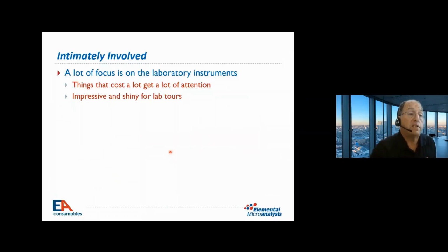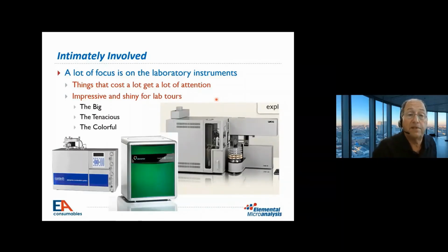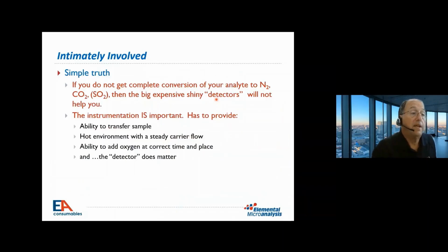But a lot of focus is always on the laboratory instruments. That's because these things that cost a lot get a lot of attention, and they're impressive and shiny for laboratory tours. There's big ones, there are tenacious ones, and there's colorful ones. But the simple truth is that if you do not get complete conversion of your analyte to N2, CO2, or in the case of SO2, then the big detectors will not really help you. The instrument is important. As we've gone through, we have to transfer the sample, have a hot environment with a steady carrier gas flow, add oxygen, and the detector does matter for sure.